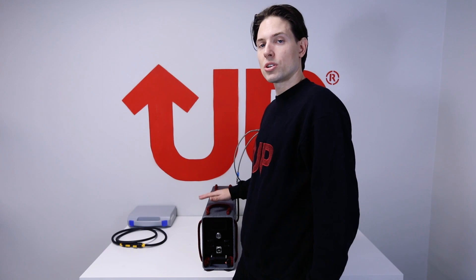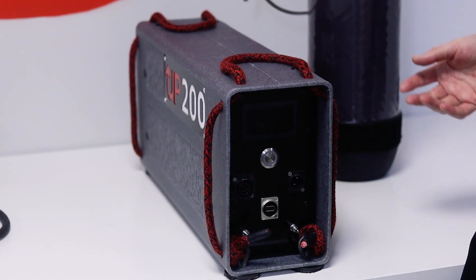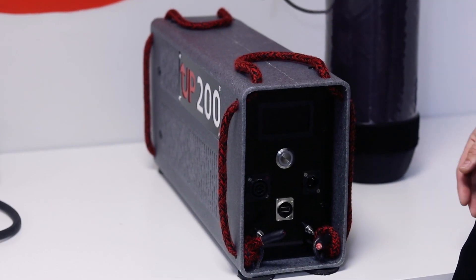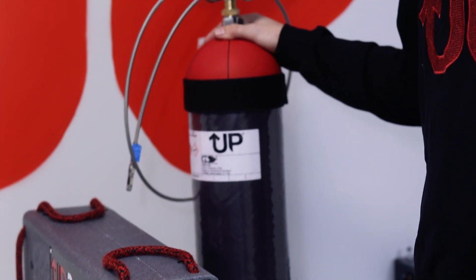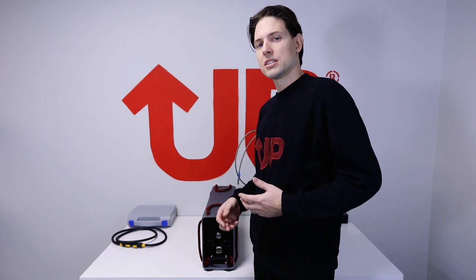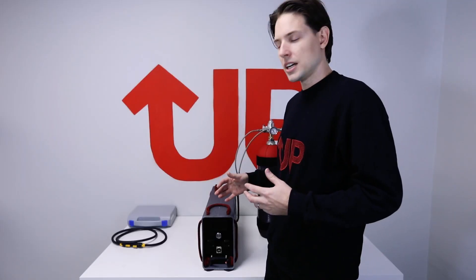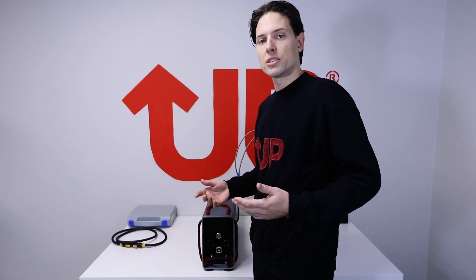UP200 requires hydrogen and oxygen to work. Oxygen is supplied from the surrounding air, which means that when you're installing the generator you need to provide enough airflow. Hydrogen is taken from a tank, and inside the generator there is no burning taking place — it's a pure chemical reaction. That's how the fuel cell works: it combines hydrogen from the tank and oxygen from the air, and the chemical reaction produces electricity, heat, and water. That's it.